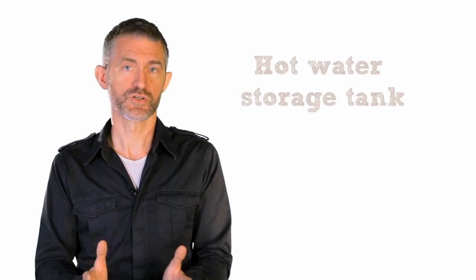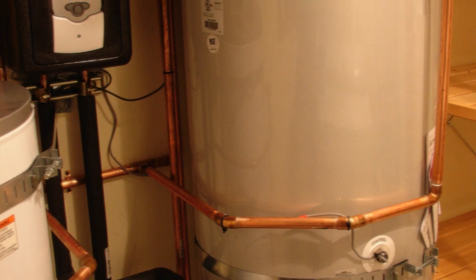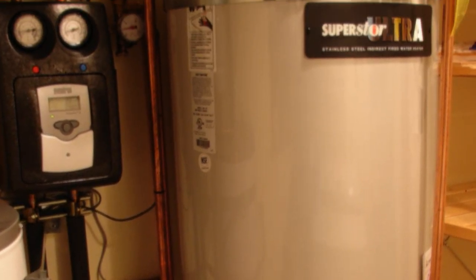Because you don't necessarily want to use all this hot water the very instant it is heated, all solar thermal systems must have a hot water storage tank. If you already have a hot water tank, you can either have an extra cylinder that works in conjunction with it, or you can have an entirely new cylinder fitted. Single cylinder systems are taller and thinner than normal immersion tanks to allow for stratification of the water, but they do take up less space overall than having two separate tanks.